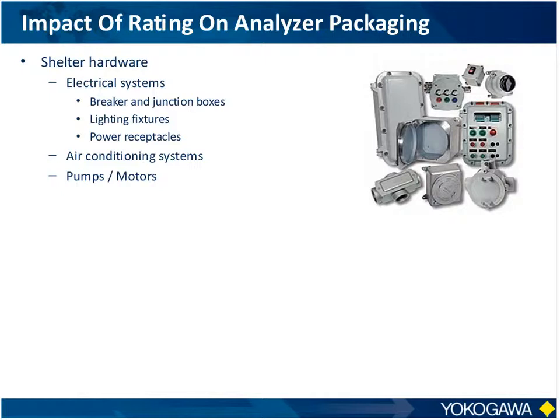These are very specialized pieces of equipment designed for hazardous areas, and the same goes for pumps and motors. If you're in an area with a lot of acetylene or hydrogen present, that's Group A and B, and those pumps and motors get extremely expensive. So it has a huge impact on overall cost.